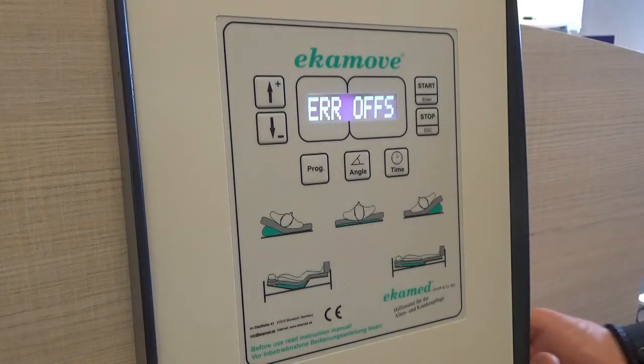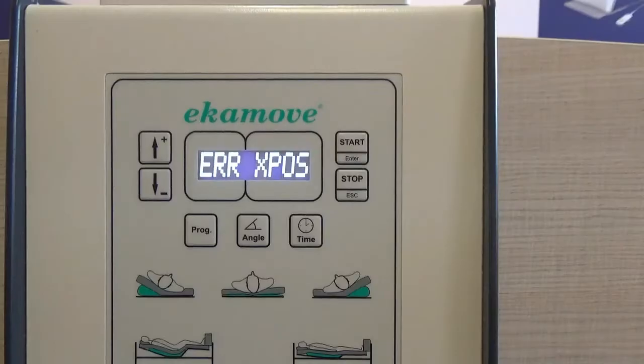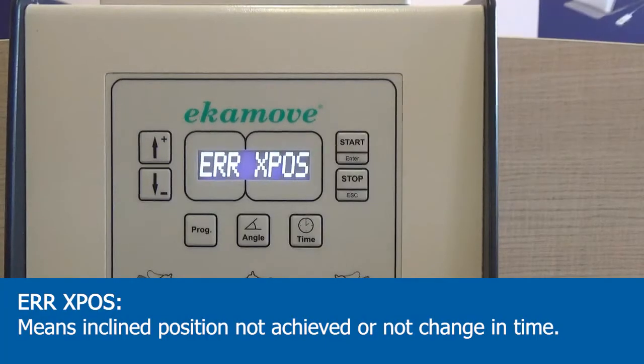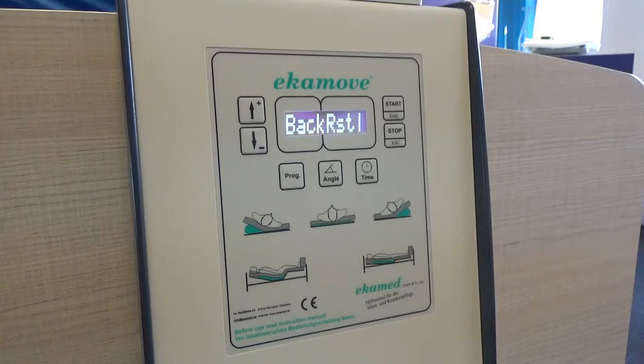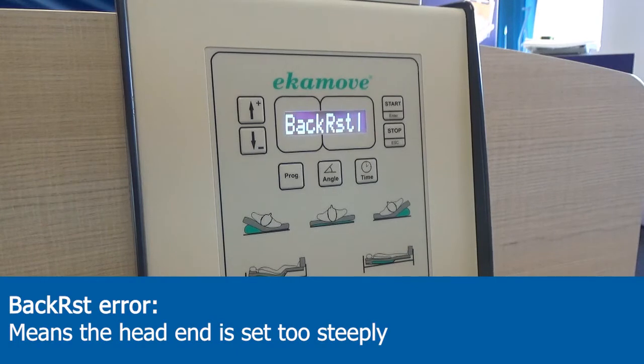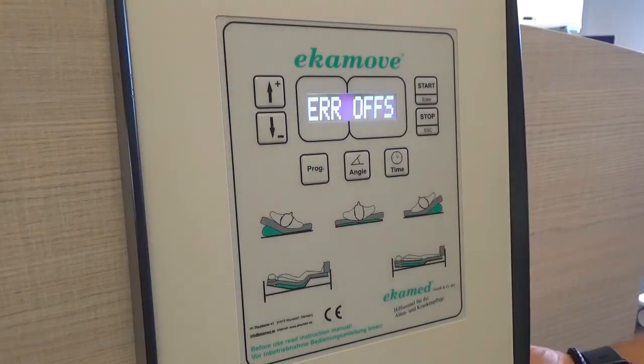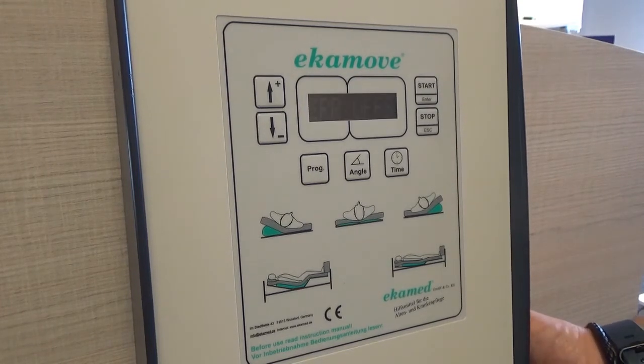For the safety of the patient, there are a number of error codes to alert you that action is required. It's XPOS error, backrest. Just lower the backrest and this will disappear from the screen and the system will restart. For all other error codes, you will be required to restart the device. Information can be found in the user manual.